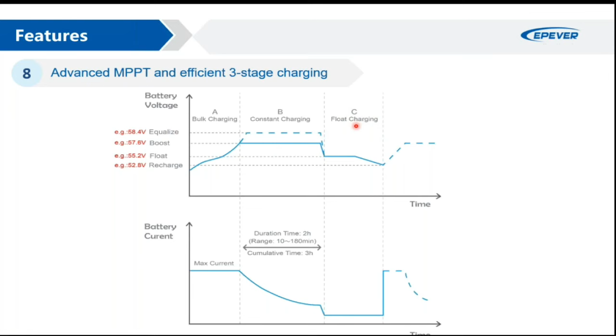There is an argument that lithium batteries don't need the float charging state. That might be true, but you can always play with these settings. If you set the float voltage lower, you can skip the float charging stage for a lithium battery very easily, just by configuring the parameters of your system.